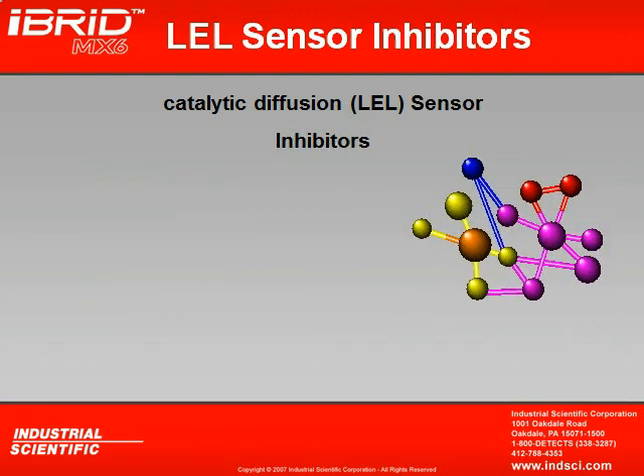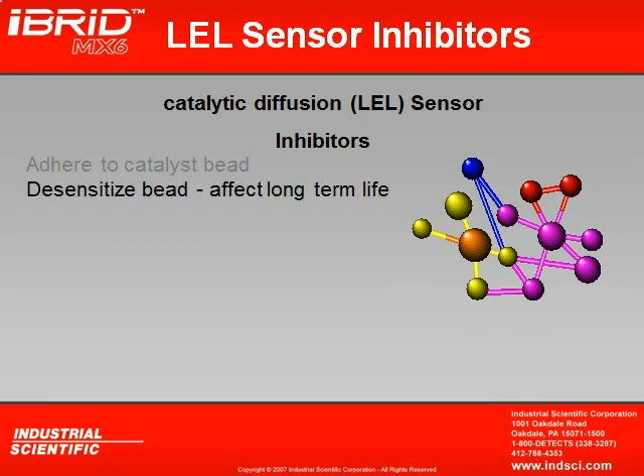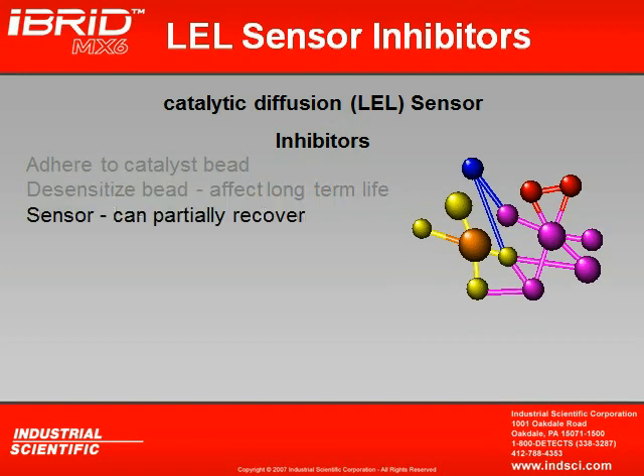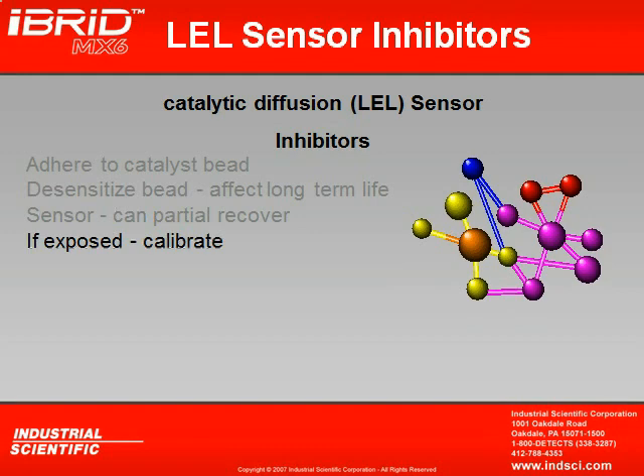Not only do we have to watch out for poisons, but we also have to watch out for inhibitors. Now, inhibitors are a lot like poisons. They adhere themselves to the catalyst bead. They could desensitize the bead, affecting the long-term life. But if there's one good thing that can be said about an inhibitor, it's this: a sensor can partially recover if it's been affected by an inhibitor. And how we make it recover is by calibrating it. Hopefully by calibrating it, we're going to burn off some of the inhibitors that have crusted themselves on the bead.